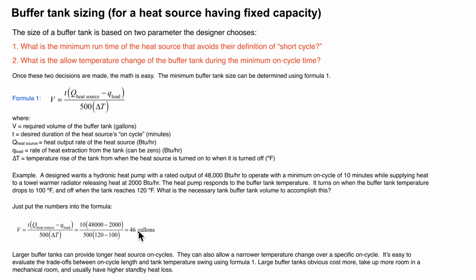So I put down here, larger buffer tanks will provide a longer heat source on cycle. So that's ultimately less wear and tear on a compressor, or in the case of a gas boiler, less wear and tear on the ignition system, okay? But obviously a bigger tank costs more money. So it is a trade-off, and different people may have different opinions on it, but I'd like to size buffer tanks so that if we're running that heat source at full capacity, we get a minimum of a 10-minute run cycle.